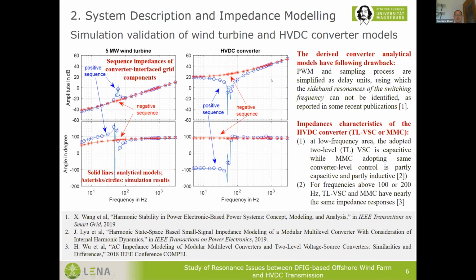And the analytical models have the following drawback, especially for high frequency dynamics. The pulse width modulation and the sampling process are simplified as a pure delay, using which the sideband resonances of the switching frequency cannot be identified, as reported in some recent publications. As for the impedance characteristic of the HVDC converter, at low frequency area, the adopted two-level VSC is capacitive, while the MMC adopting same converter level control will be partly capacitive and partly inductive. For the frequencies above 100 or 200 Hz, the two-level VSC and the MMC will have nearly the same impedance responses.